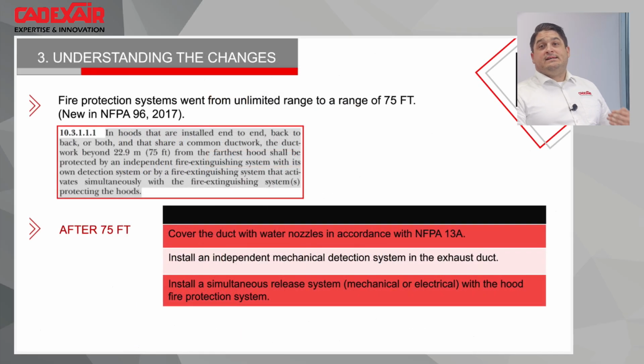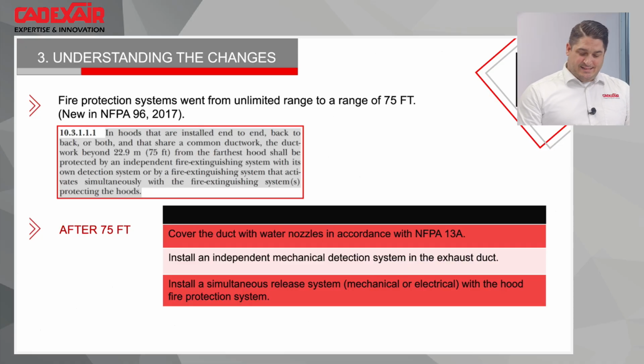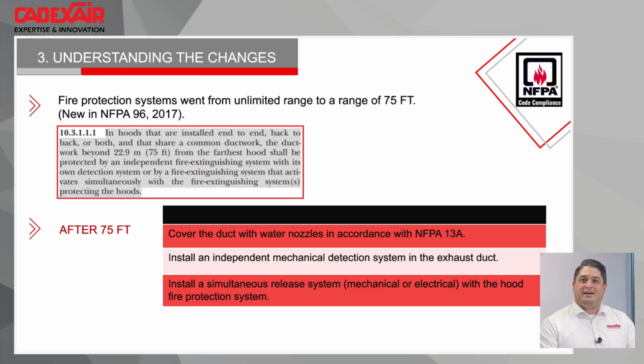Now the new change. This is the new stuff, and I will say this one is not really fun, but that's why the kitchen exhaust hood business is interesting. It's always moving and always has some challenges in it. So now, if we go back in time and we want to list the fire protection system, you can knock at the UL door and say, I want to list my fire protection system as per UL 300. You will have a bunch of tests to do. But when you do it, you have three choices. You can be listed for 10 feet, 25 feet of ductwork, 50 feet of ductwork, or 75 feet of ductwork.